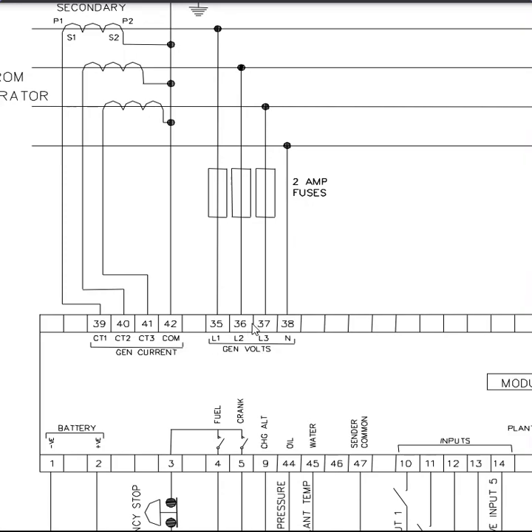Now 35 to 38 is L1, L2, L3 and neutral. So you're going to tap off of the breaker. A lot of the time there will be spade spots to hook up to get sensing from each of the legs so that it can tell you what voltage it's at. 2 amp fuses on the 1, 2, and 3 phases. The neutral does not need to have a fuse.